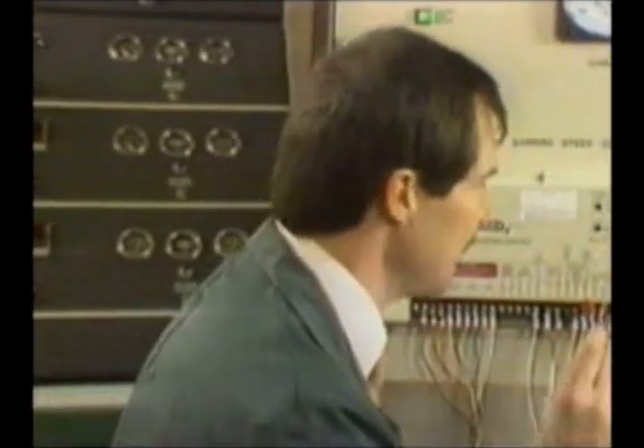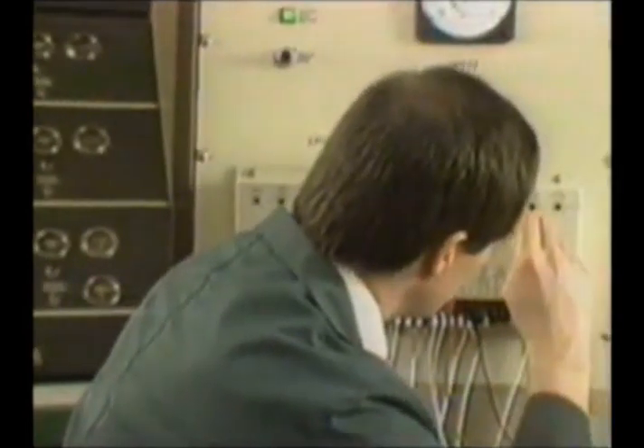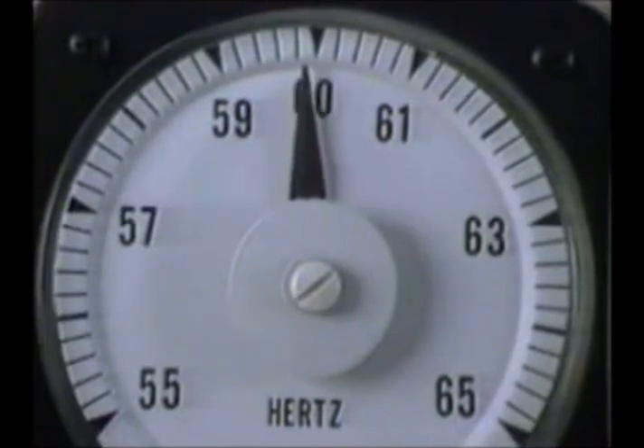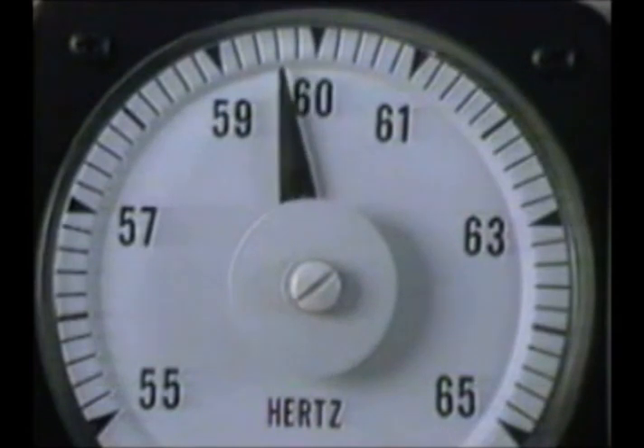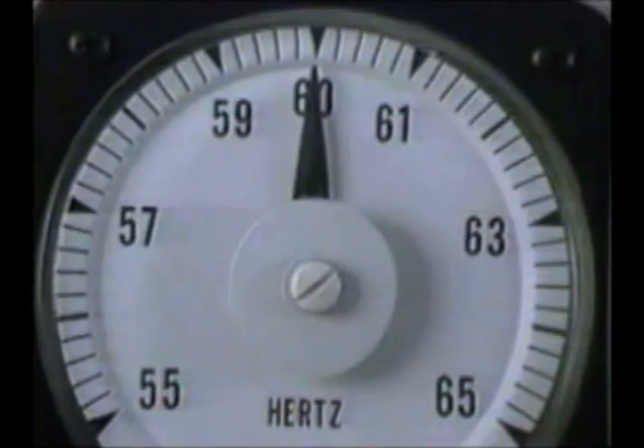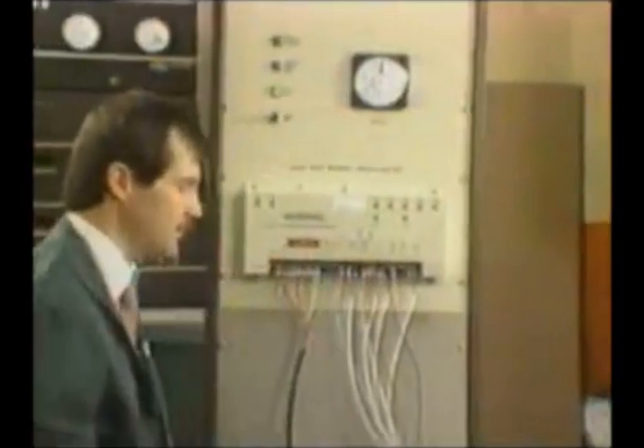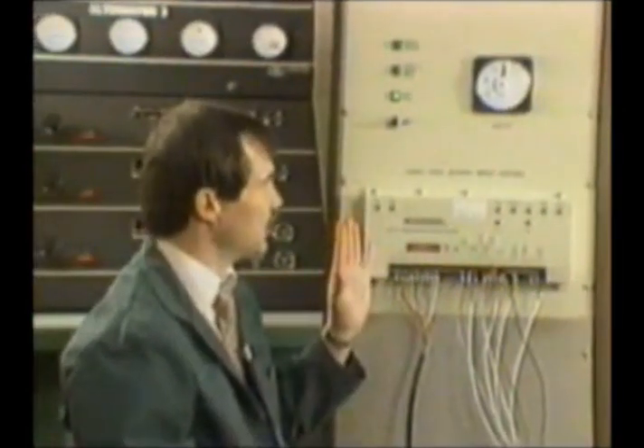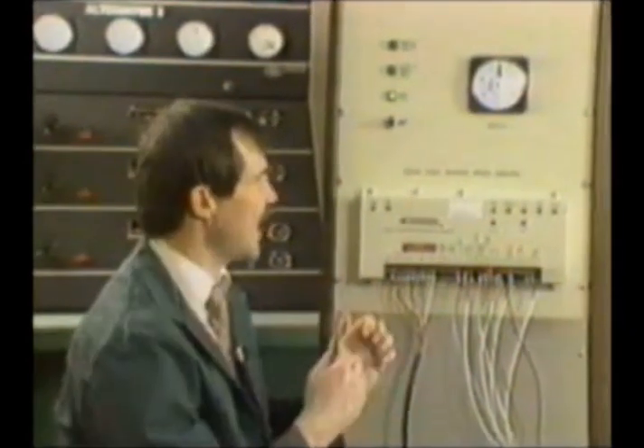But what I'm going to do to demonstrate for you, I'm going to turn my reset pot up to 8 on the dial. On the dial of 0 to 10, I'm now set up at 8. Now I want you to watch the Hertz meter again as I put the loads on. I'll put on the 25 kW load. Now the 50 kW load, it takes a lot longer to come back to the 60. And that's what the reset will do for you. It's going to take longer for it to come back, so that's taking too long.